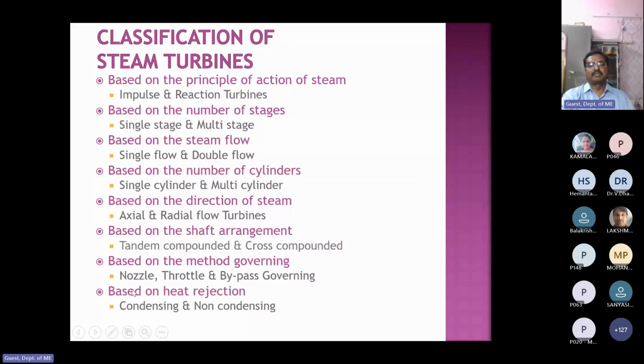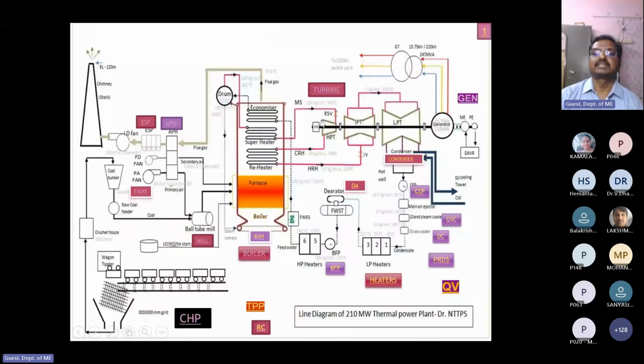Next classification is based on heat rejection. The heat rejection is done at the condenser. If we utilize the condenser, those are called condensing turbines. If we are not using the condenser, those are non-condensing turbines. In textile or petrochemical industries, they need low pressure steam for process heat. In that case, steam from the last stages of the turbine goes directly to process heating, so a condenser is not required. But in a thermal power plant, where power generation is the only aspect, I use a condenser only. There are so many advantages of the condenser. We will discuss that next. So in a simple way, we discussed the turbine.